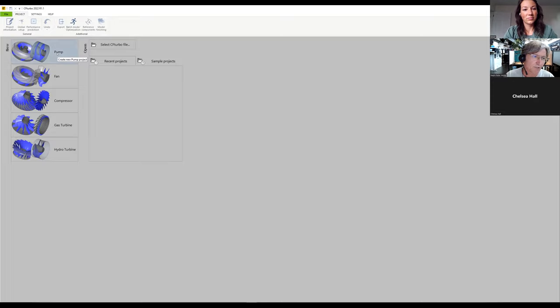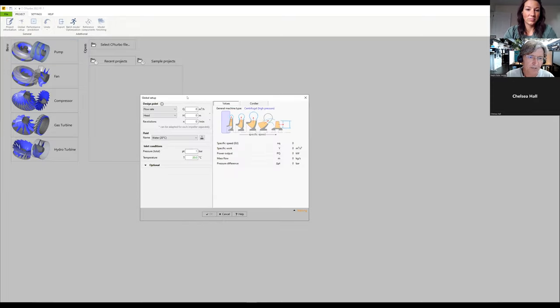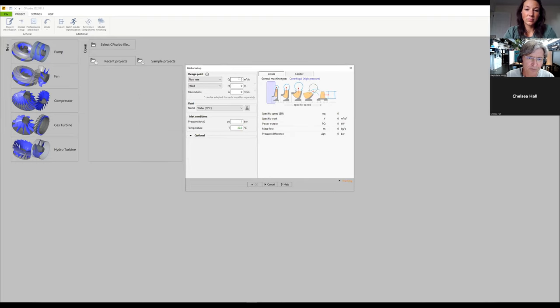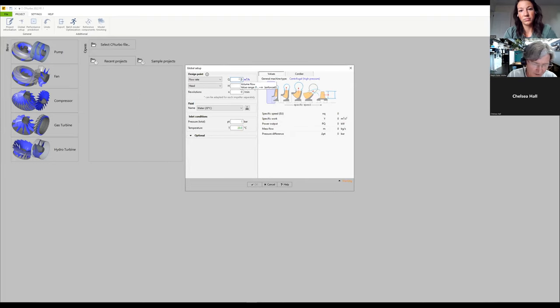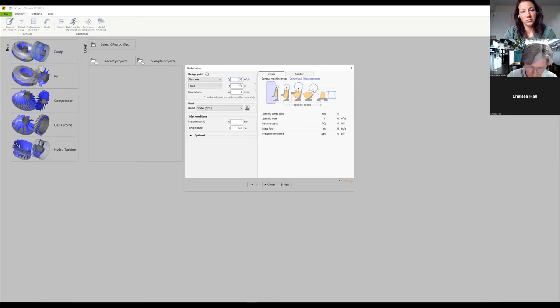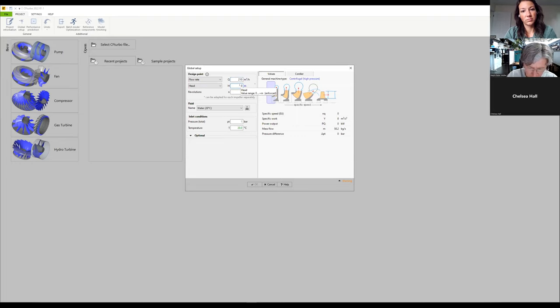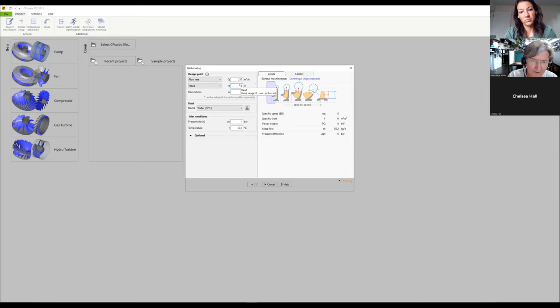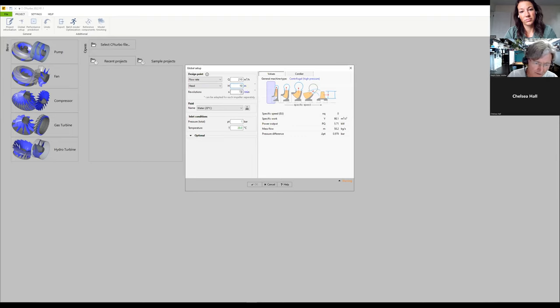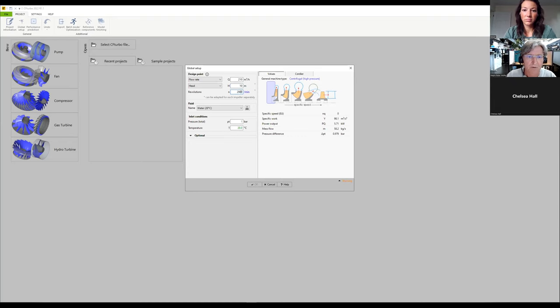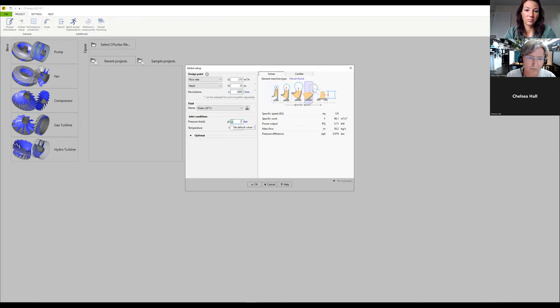First, we need to have a design point in the range of the pump we want to remodel. Here I have a flow rate of 210 cubic meters, a head of 10 meters, and a rotational speed of 2900 RPM, which will give us a mixed flow impeller.